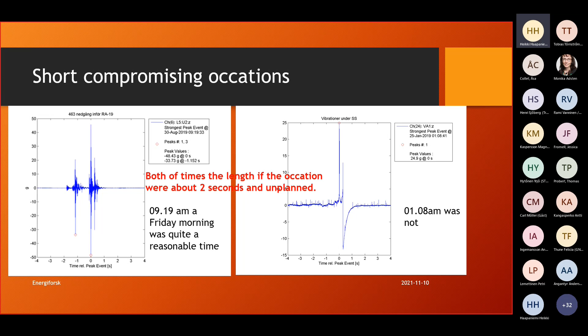Then you come to this very significant happening, a turbine stop. It happens that we have this type of transient 4, 5, 6 times during a period of 15 minutes after the turbine stops. So the turbine stop itself wasn't the highest transient - the highest transient came about 3 minutes after.